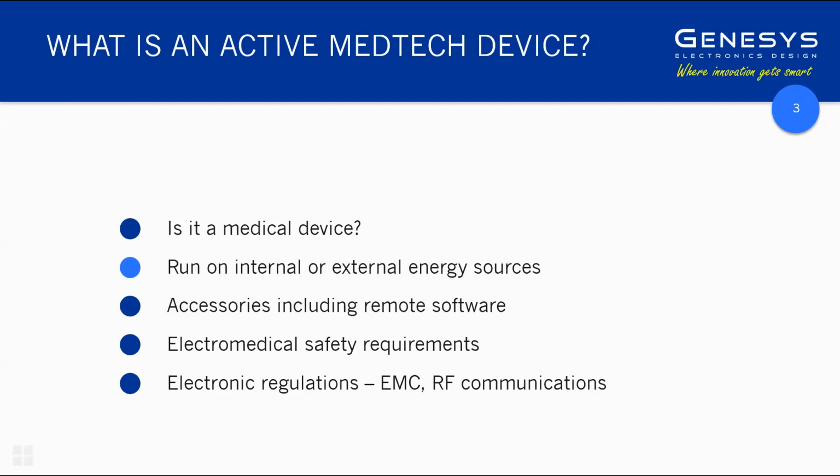But the main thing that really differentiates active medtech from a whole range of other technologies is the higher regulatory burden around safety. Obviously, anything with electricity has its own requirements that would be standard to any electronic device, but the burden of regulatory compliance is much, much higher for medical devices.